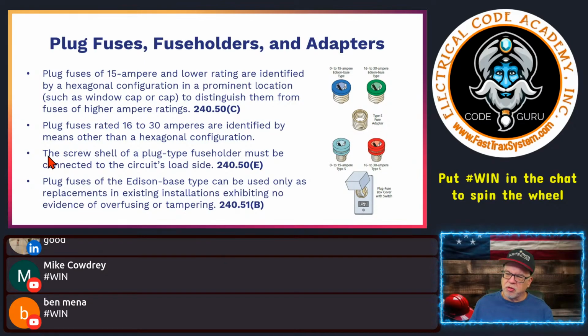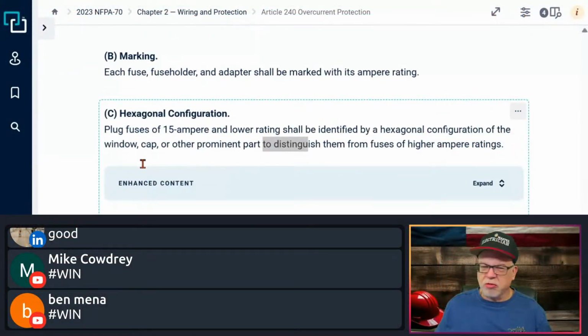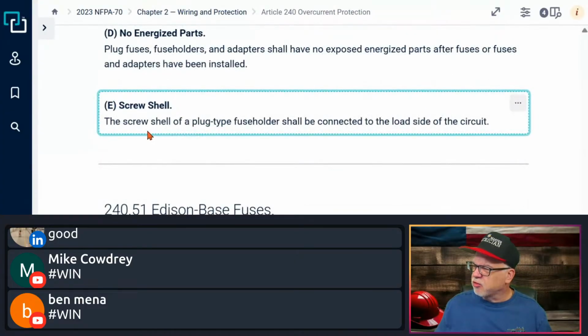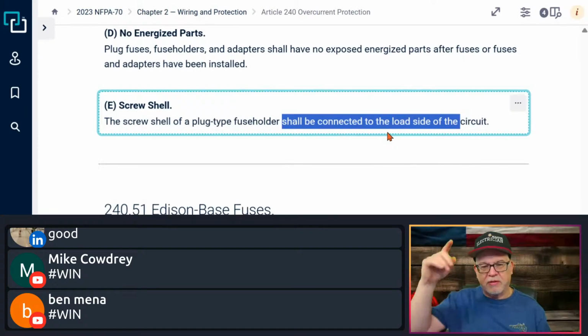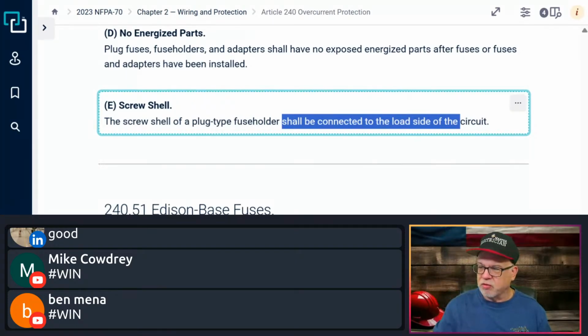And it says the screw shell on the plug type fuse holder must be connected to the circuit's load side. Okay, so the screw shell, right? So 240.50(E). We'll look at that. Here's your screw shell statement right here. E. It says the screw shell of a plug type fuse holder shall be connected to the load side of the circuit. Absolutely. So it's coming through, coming down, connected to the load. Screw shell is going out, and it's going out to supply the load through the fuse itself. Okay, so coming in through the tab, going out through the shell.